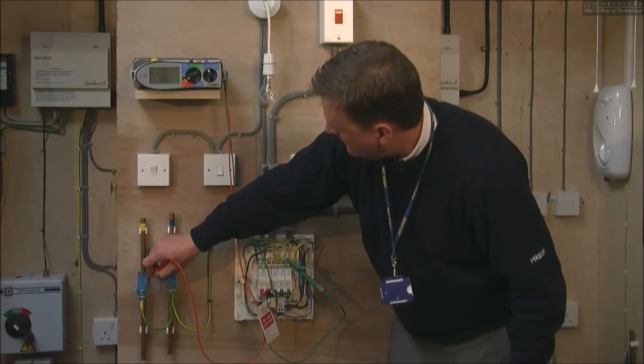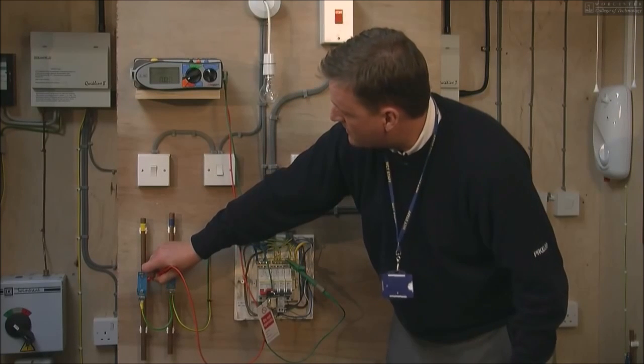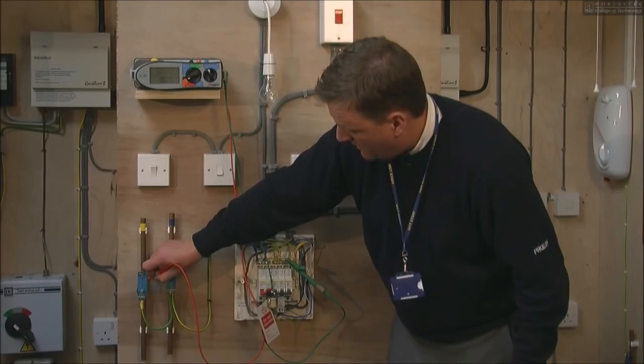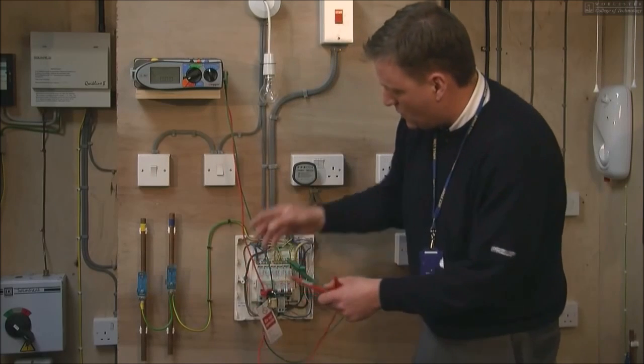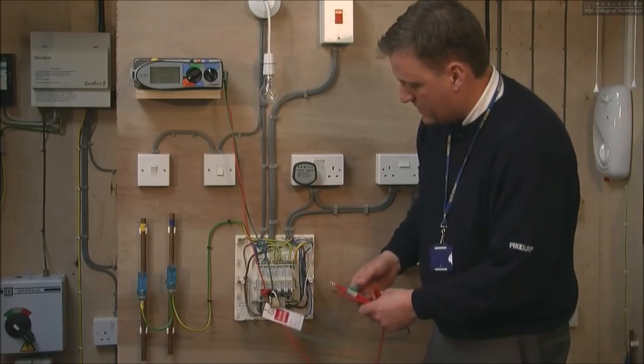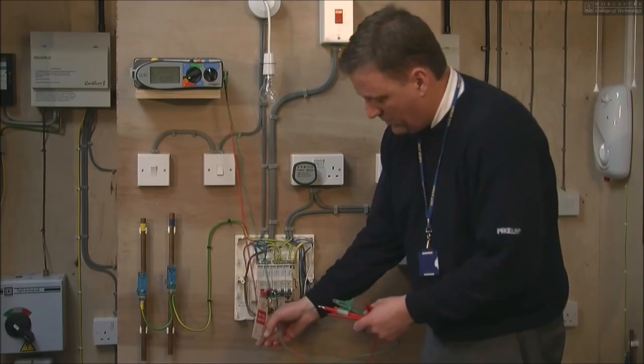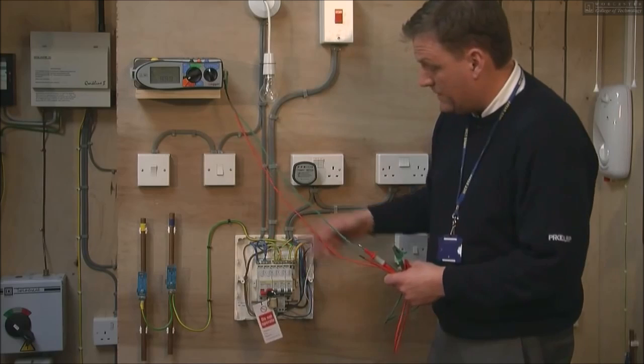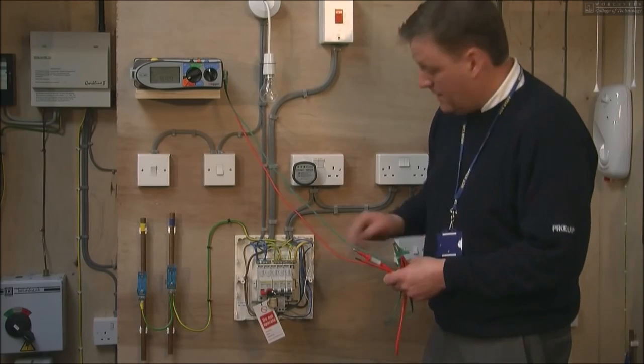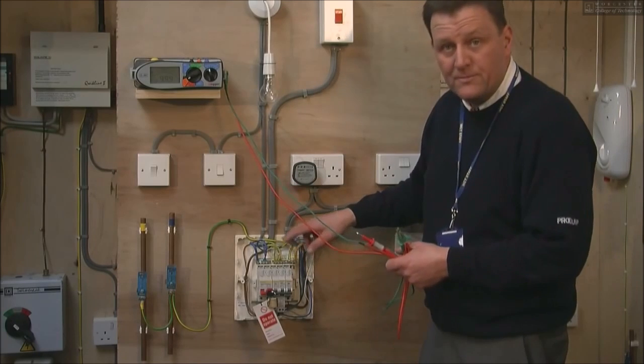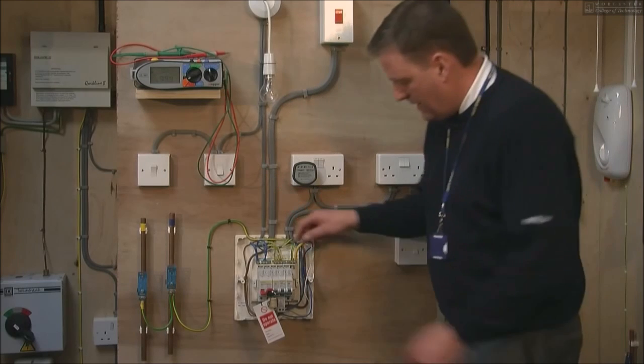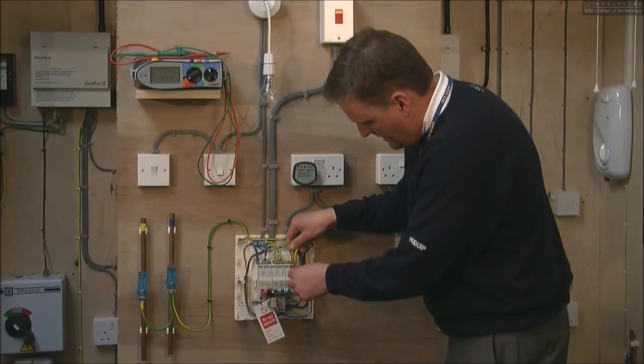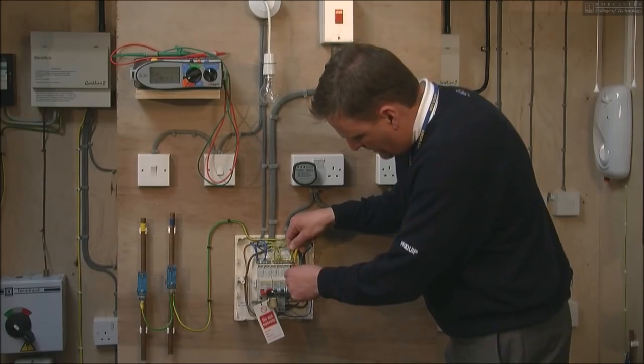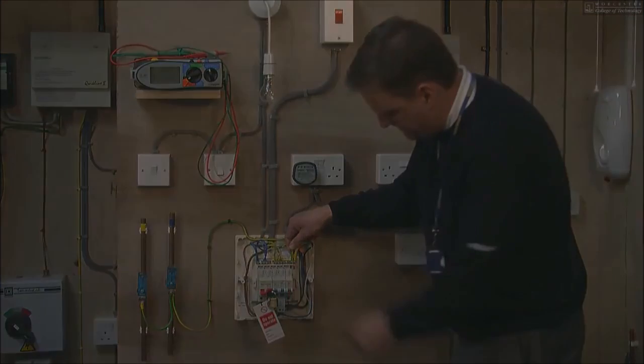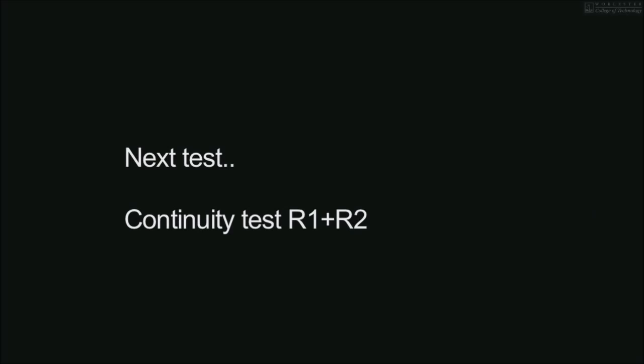and the gas. As you see, the readings are coming out at 0 ohms, mainly because the circuit is very, very short and there isn't very much resistance in the circuit. Under normal conditions, anything above 0.05 of an ohm, the conductor would actually have to be renewed to a bigger size. Remember to reconnect the protective bonding conductor and make sure the connections are nice and tight.